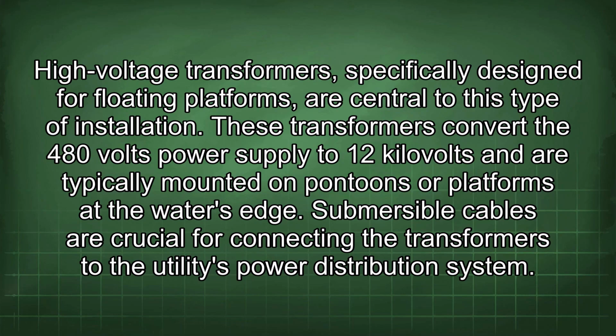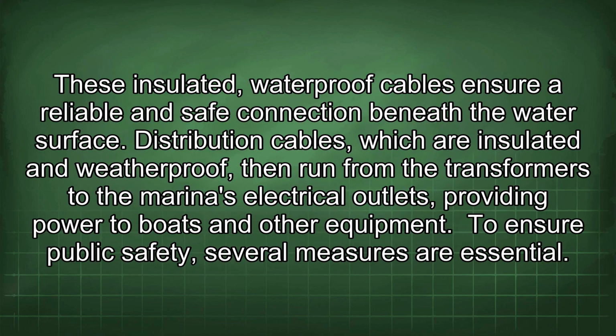High-voltage transformers specifically designed for floating platforms are central to this type of installation. These transformers convert the 480 volts power supply to 12 kilovolts and are typically mounted on pontoons or platforms at the water's edge. Submersible cables are crucial for connecting the transformers to the utility's power distribution system. These insulated, waterproof cables ensure a reliable and safe connection beneath the water surface.